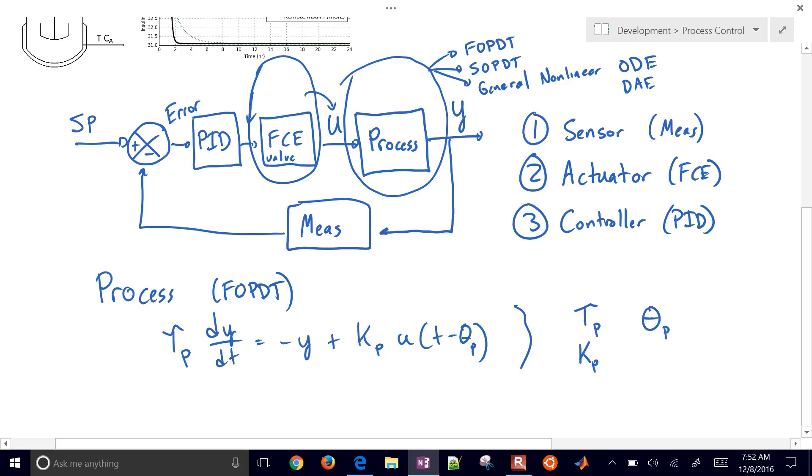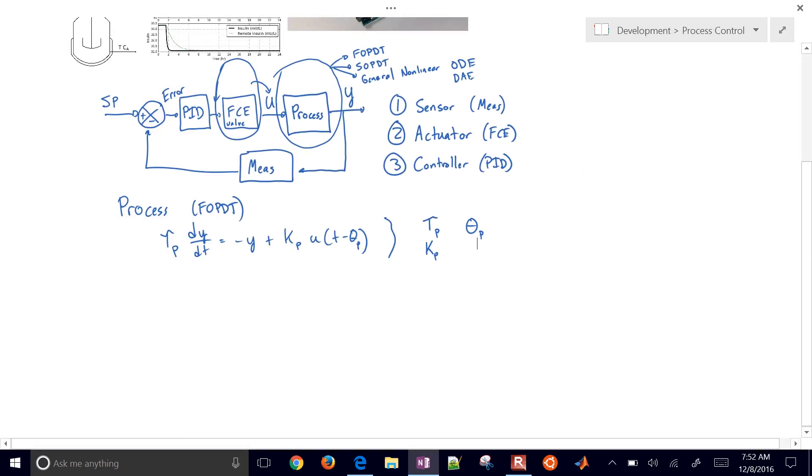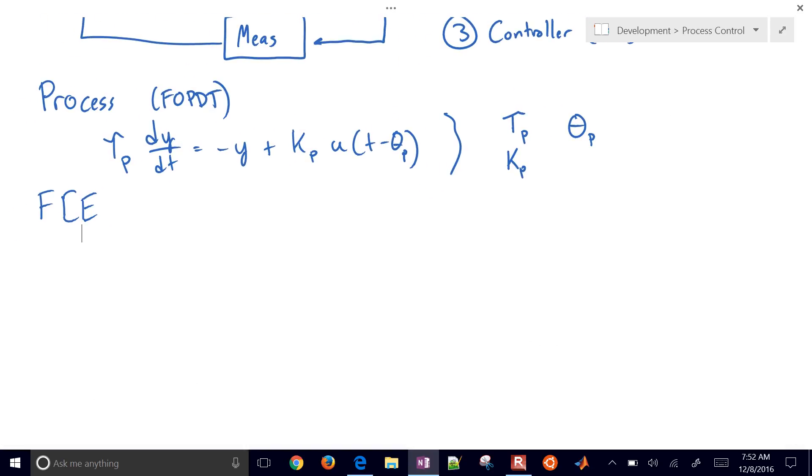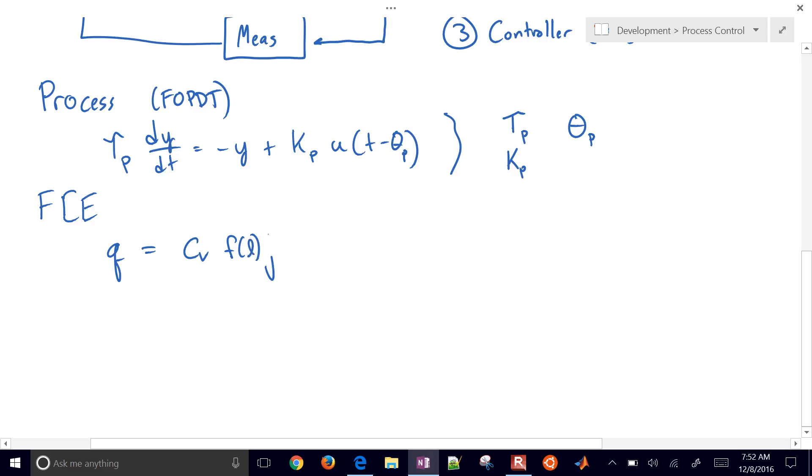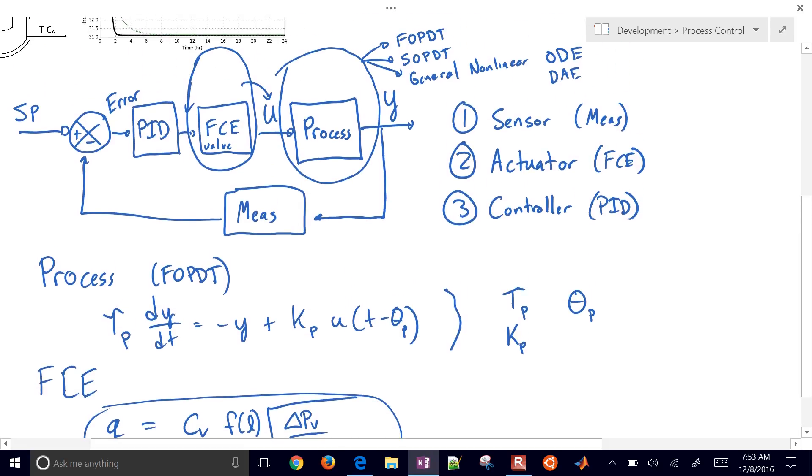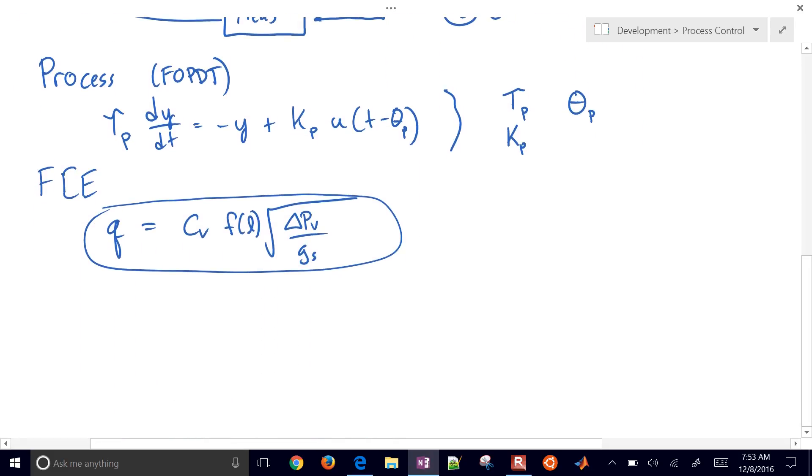Our final control element is going to be characterized by a valve. So final control element. And one of the equations that we're going to be using for this part of the course is going to be the valve equation. The flow rate through the valve is going to be equal to a C_v value times a lift function times the square root of the pressure drop across the valve divided by the specific gravity of the fluid.